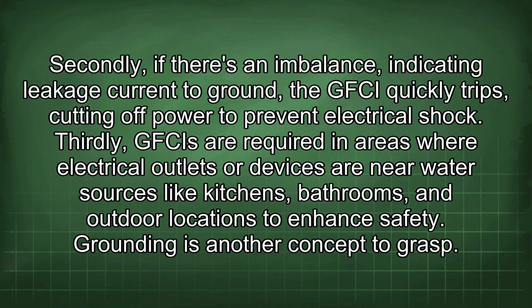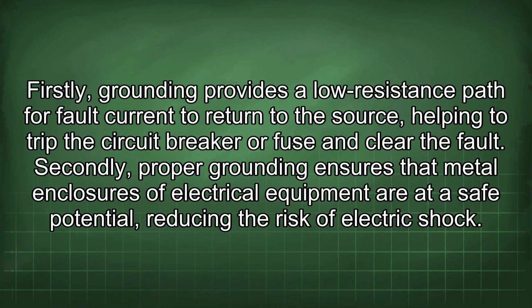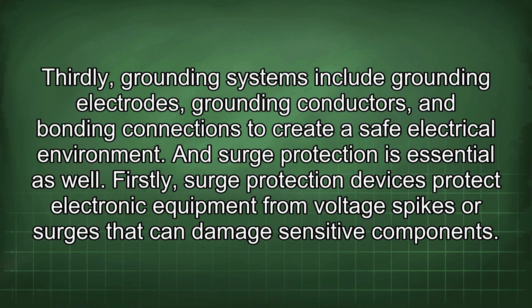Grounding is another concept to grasp. Firstly, grounding provides a low resistance path for fault current to return to the source, helping to trip the circuit breaker or fuse and clear the fault. Secondly, proper grounding ensures that metal enclosures of electrical equipment are at a safe potential, reducing the risk of electric shock. Thirdly, grounding systems include grounding electrodes, grounding conductors, and bonding connections to create a safe electrical environment.